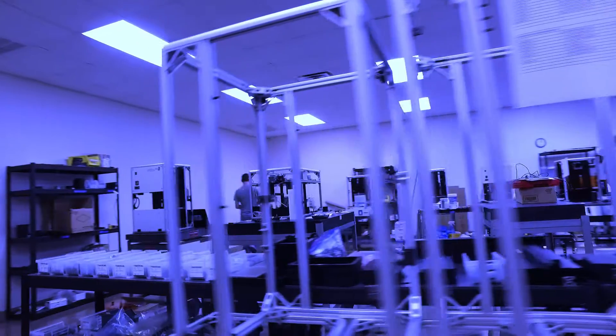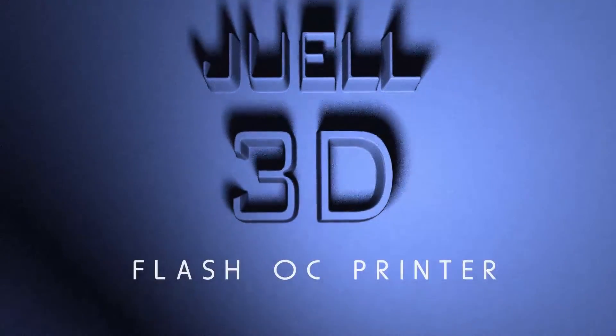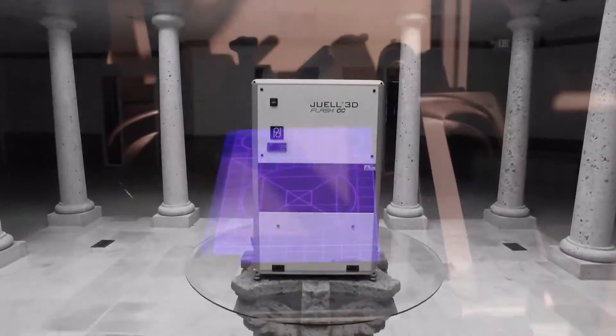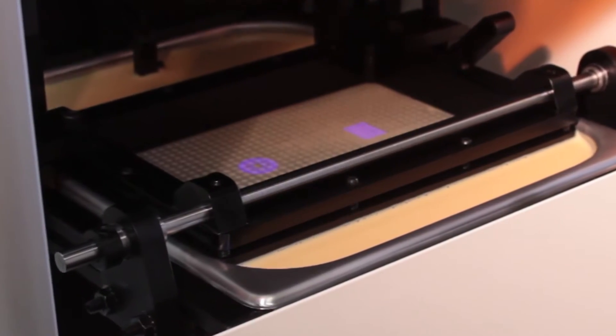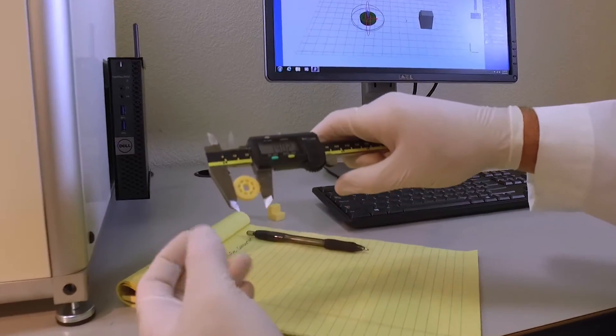From Park Dental Research comes the Juell 3D Flash OC printer, designed specifically for the dental industry. Unlike most 3D printers, the Juell Flash OC builds its 3D models on a patent-pending oxygen permeable mask, a technology unavailable from its competitors. This unique process creates smooth surface models of high resolution and precise anatomical accuracy.